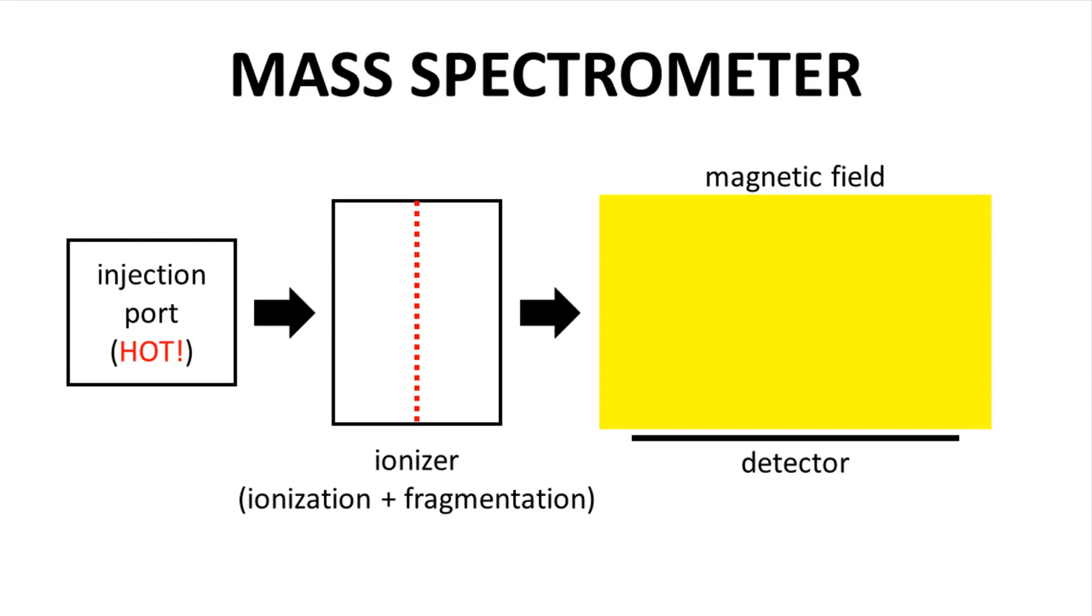Running the mass spectrum begins with introducing the sample molecule into the mass spectrometer. Often a tiny sample of the molecule or mixture is injected into a heated port. The sample boils, vaporizes, and the gas is swept into the ionizer.